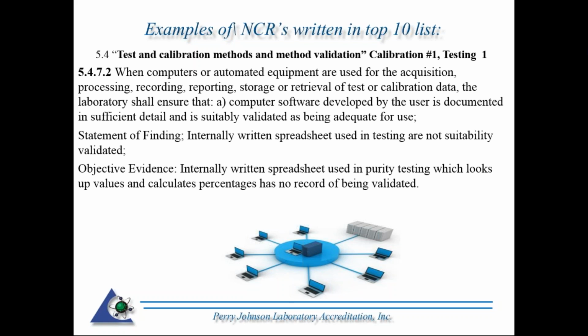This particular finding was written in regards to an internally written spreadsheet used in testing not being suitably validated. The objective evidence was a spreadsheet that was actually seen in purity testing, which looks up values and calculates percentages, and has no record of being validated. Excel itself, let's say for example, does not need to be validated. But if you're taking Excel and writing your own formulas and the spreadsheet is doing calculations and looking up values, then you need to validate it.